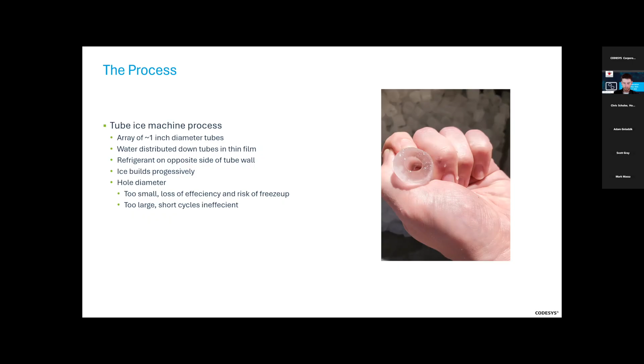So we have an example here of a plate ice machine. Despite me talking about tube ice the whole time, this is a recent plate machine we did with CODESYS. And this kind of gives a nice visual overview. And in this scenario, it was a turbo machine with 6 sets of plates that build plate ice. It's the same process as building tube. It's just the water goes down the side of the plate, the refrigerant's on the inside, and when we go into that defrost, instead of a cutter, the plates just fall and shatter.